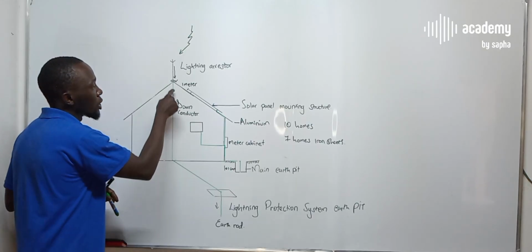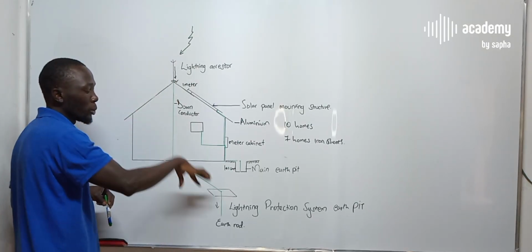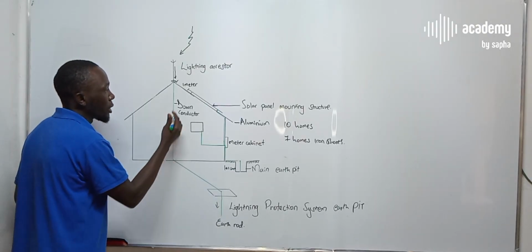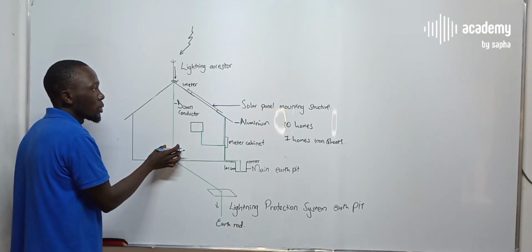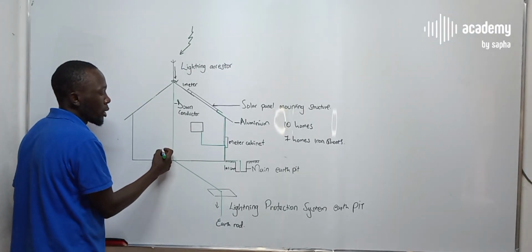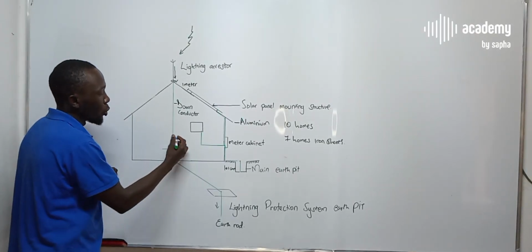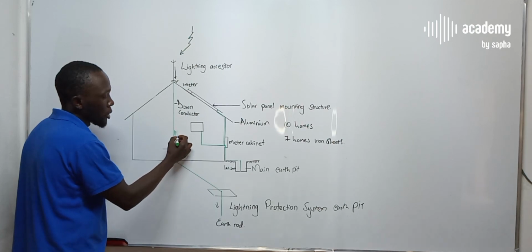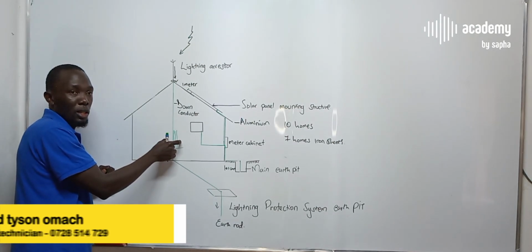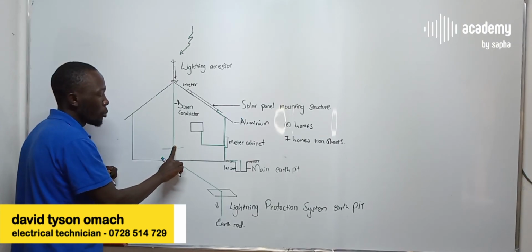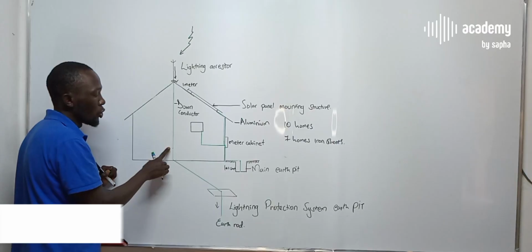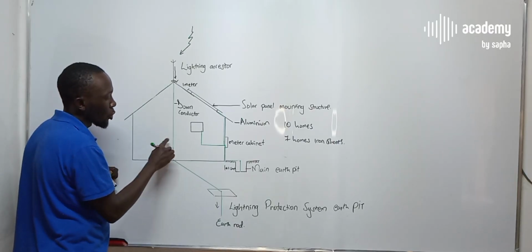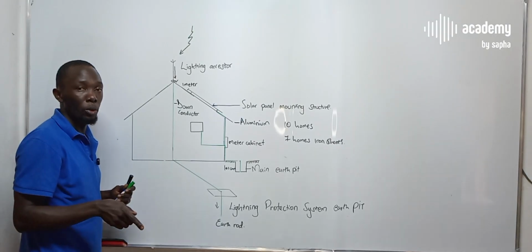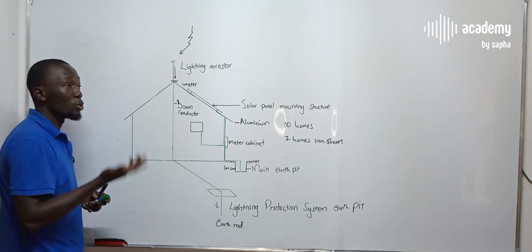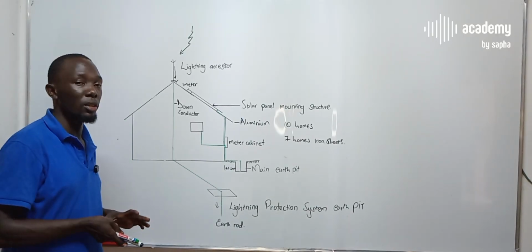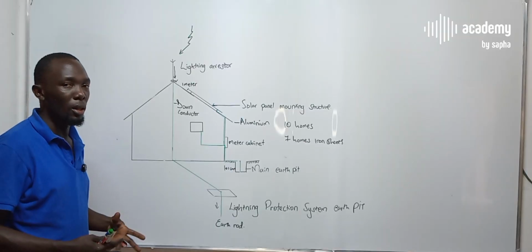or cables. So you use a path where this cable just goes from the antenna all the way to the ground without having to cross, either probably on the wall section outside here or on top of the roof, other electrical cables, or to lay alongside other electrical cables very close to each other. So you pick a path that you know no more electrical installation work is going to happen, to avoid laying it either close to other electrical cables or across electrical cables. So that is to prevent things like induction, electromagnetic interference, or even the arc flash, and very many other issues.